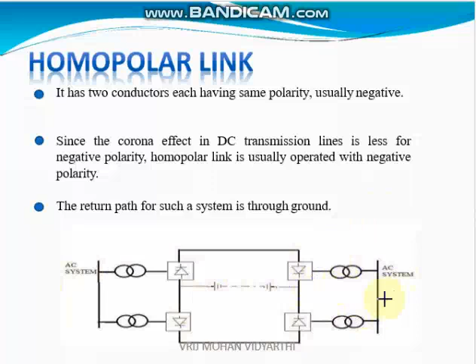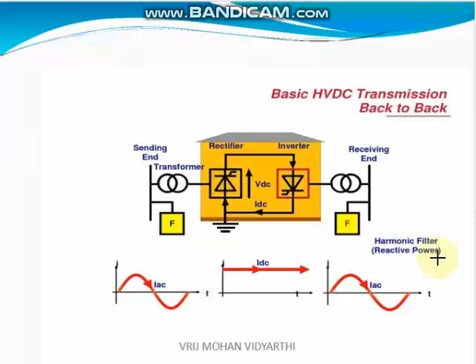Basic transmission of HVDC: back-to-back transmission, point-to-point overhead lines, point-to-point underground cable transmission, point-to-point submarine transmission. This is a basic HVDC transmission for back-to-back. This is a diagram. Sending end transformer for step-up, rectifier for converting, inverter to convert again from DC to AC, and we again step down here at the receiving end. This is the ground. This is the waveform, AC to DC. Then there is the harmonic filter, which is used to filter out the harmonics.